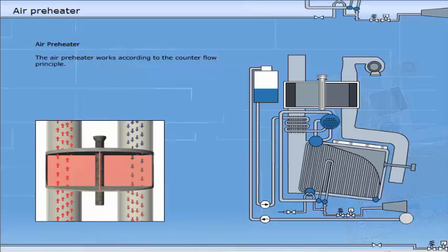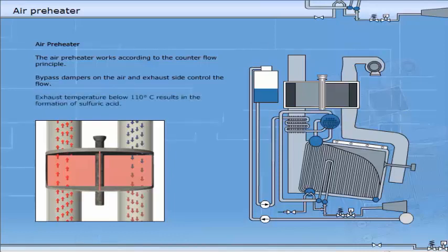The air preheater works according to the counterflow principle. Bypass dampers on the air and exhaust side control the flow. Exhaust temperature below 110 degrees centigrade results in the formation of sulphuric acid.